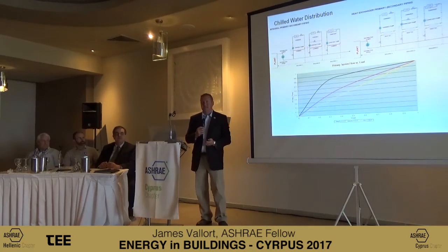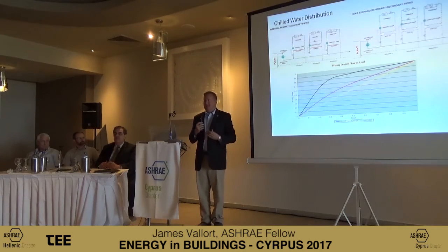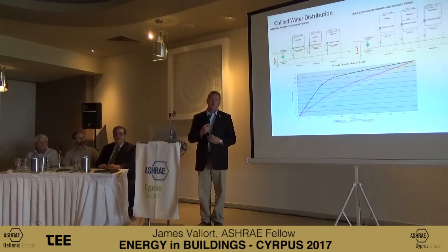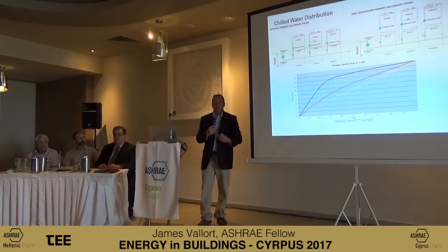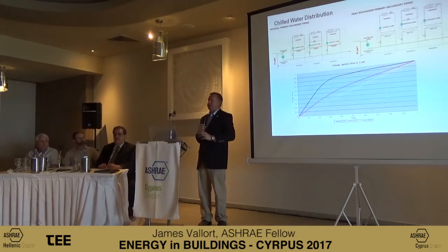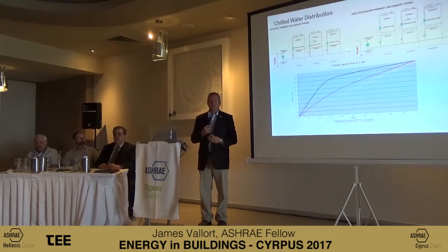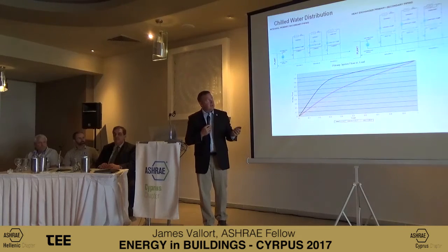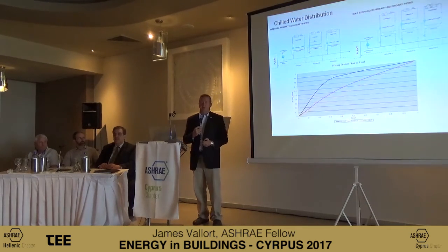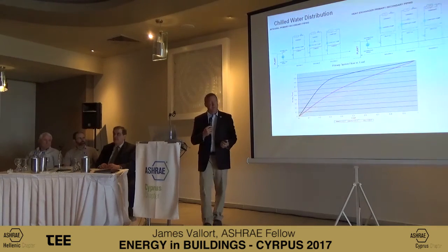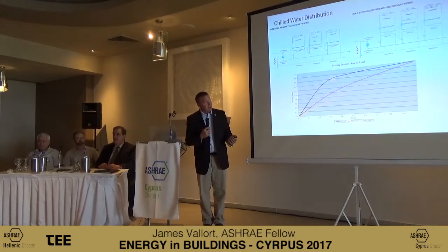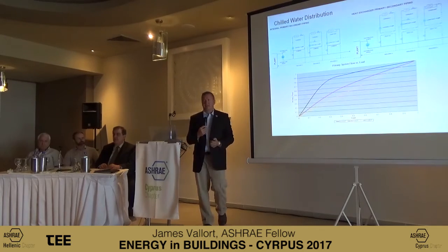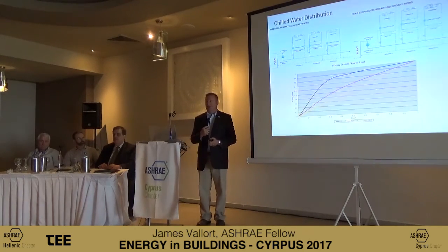We maintain efficiency by maintaining our delta T. When we look at central plants, we need to examine how chillers are tied into the plant and how buildings and loads are tied into the distribution. Often you get called to a facility and they say they need you to optimize the central plant — but I'll go look at their buildings and check flow rates and delta T's in each building. They might say the problem isn't the central plant, but the distribution is what impacts it. On paper we design with a nice ideal line, but buildings often run far below that, doing society an injustice by operating at an efficiency nowhere near what the system is capable of.